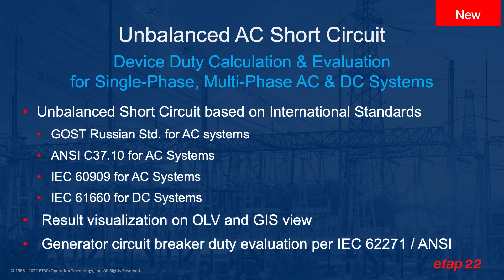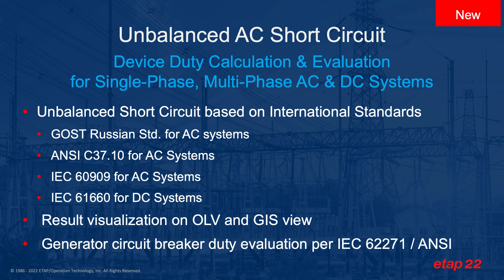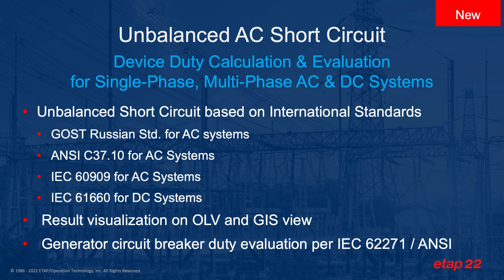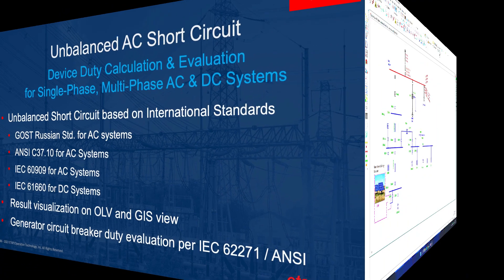The standards that are supported by unbalanced short circuit include GOST Russian standard for AC systems, ANSI C37 also for AC systems, IEC 60909 for AC systems, and IEC 61660, which is meant for DC systems. You can have the result visualization on the single line diagram as well as the geospatial diagram. And the generator circuit breaker duty evaluation is also included per IEC 62271.